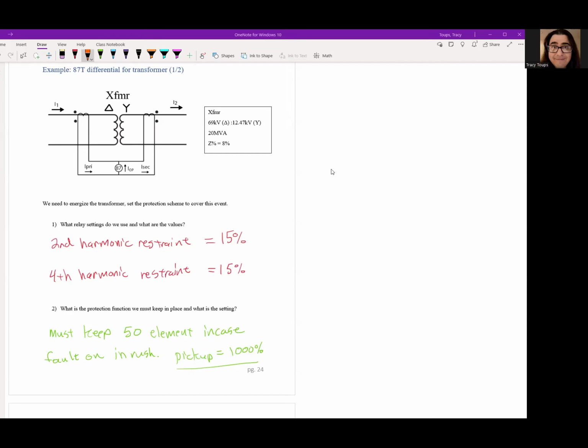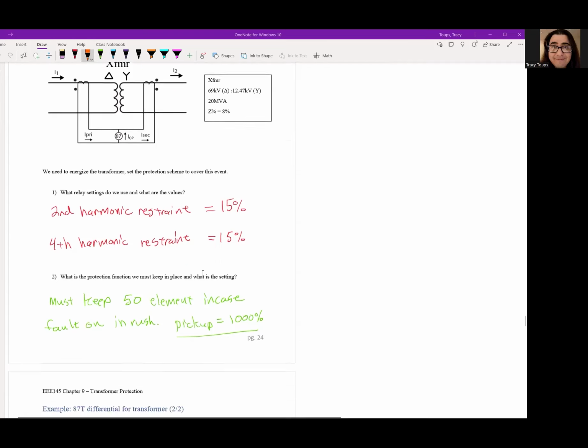Okay, and what is the protection function we must keep in place, and what is the setting, just in case something goes wrong? We must keep a 50 element in case there's a fault on inrush. And the pickup for this 50 element is typically 1000% or 10 times your load current. Okay, because if there's going to be a fault internal to the transformer, it's going to be a really, really high current. It's going to go most likely way above this 1000%. Okay, so that's how you set for inrush.